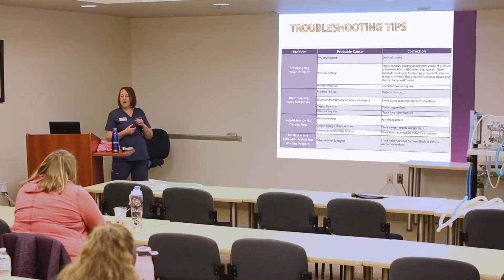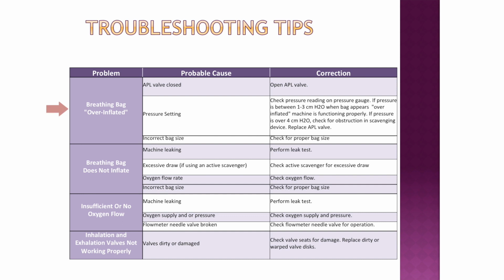Okay. Other troubleshooting tips: if the bag is overinflated, make sure your pop-off is open. The pressure on the gauge, 1 to 3 centimeters, can be normal, especially for these ventilators. They're all designed to operate with about 5 centimeters of PEEP, and if they lose that 5 centimeters of PEEP, they won't work properly. There'll be alarms associated with that.